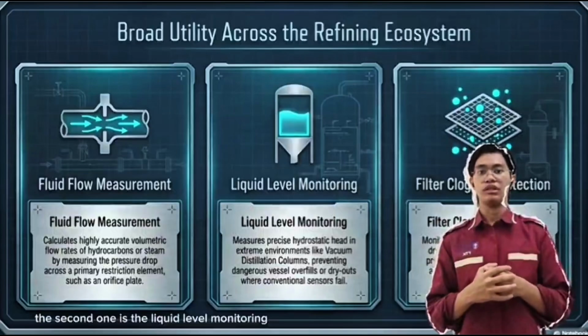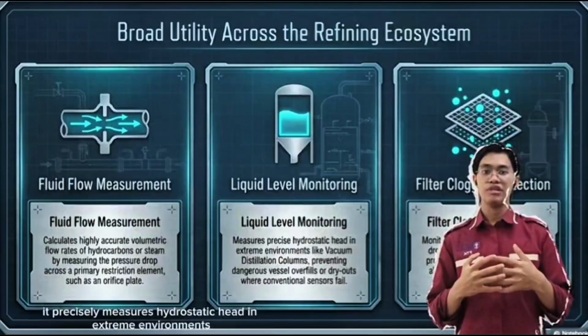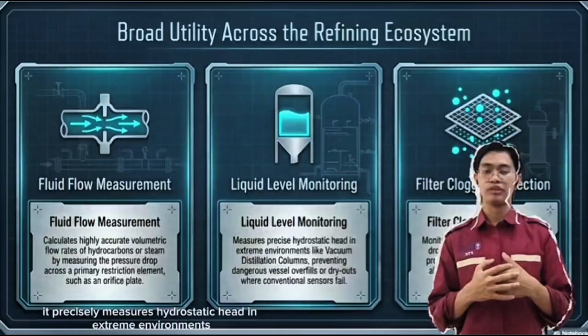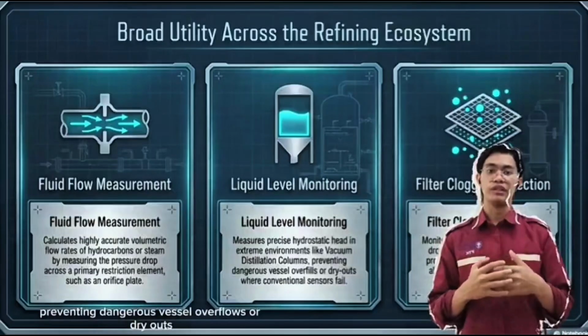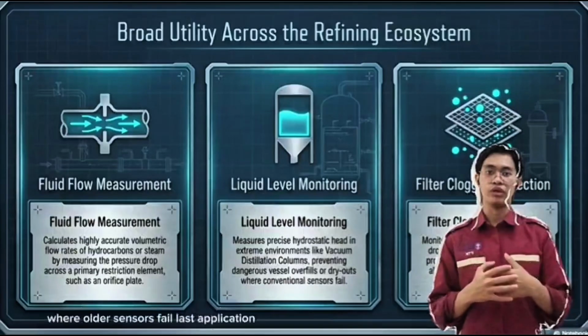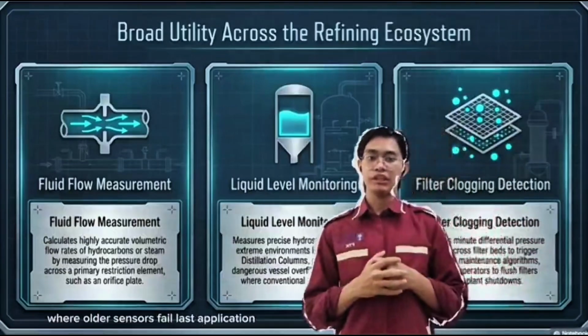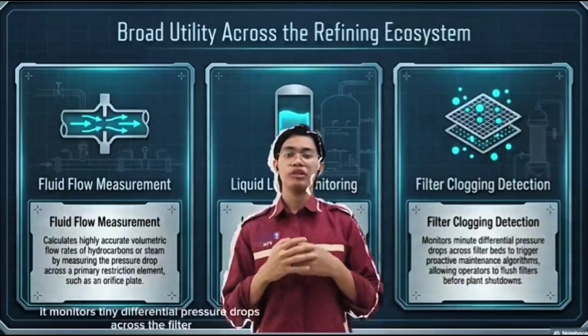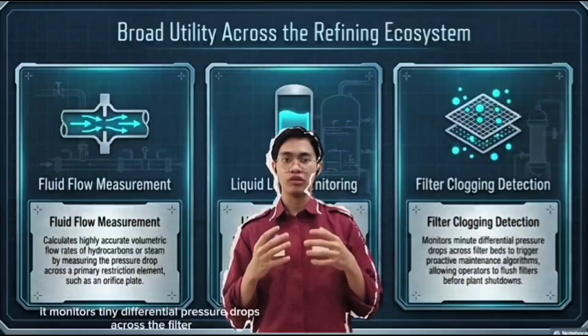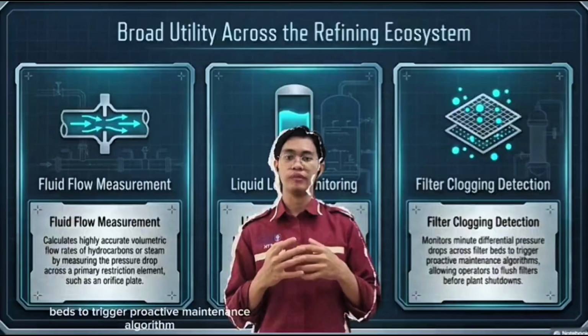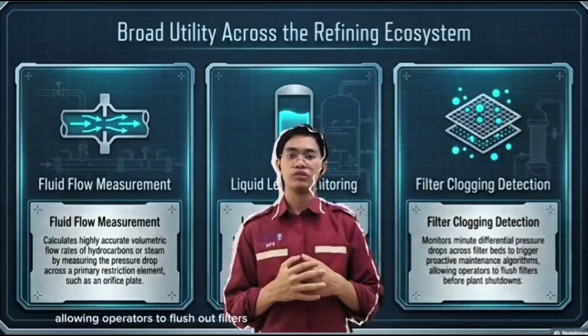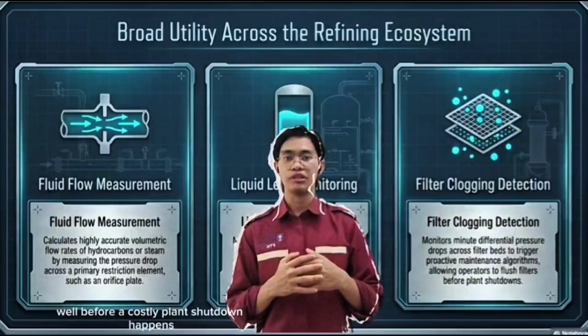The second one is liquid level monitoring. It precisely measures hydrostatic head in extreme environments like a vacuum distillation column, preventing dangerous vessel overflows or dry outs. The last application is filter fouling detection. It monitors tiny differential pressure drops across the filter beds to trigger proactive maintenance algorithms, allowing operators to flush out filters well before a costly plant shutdown happens.